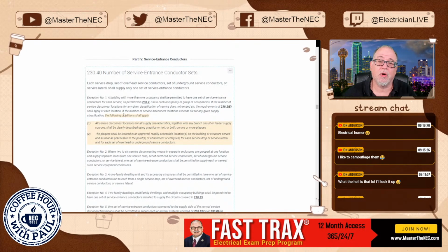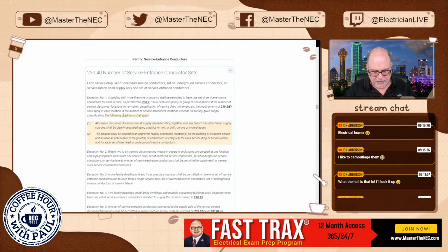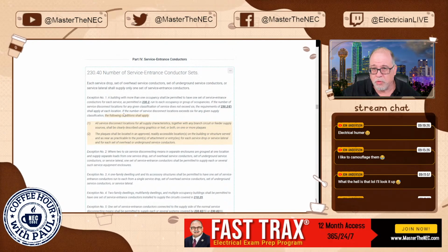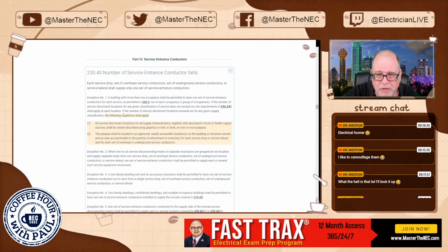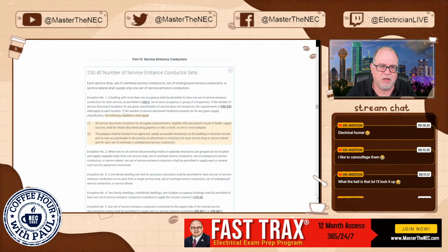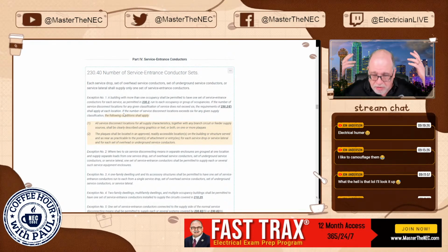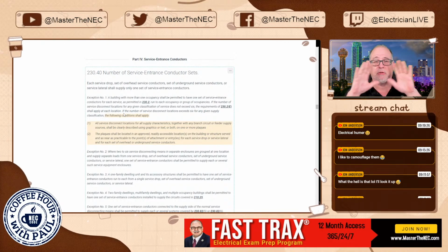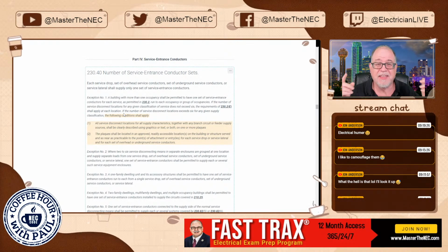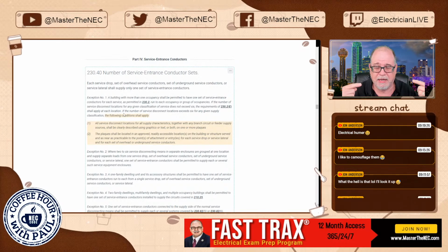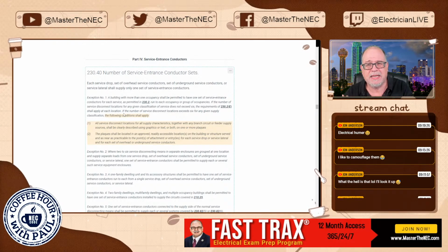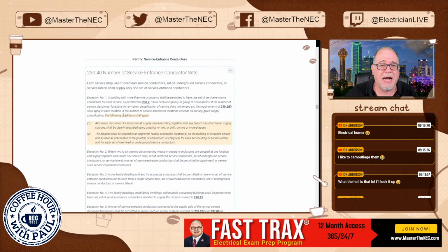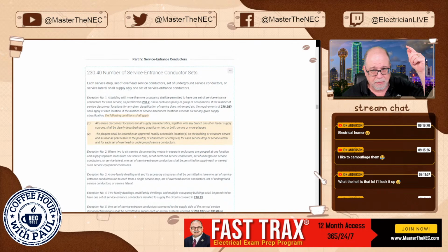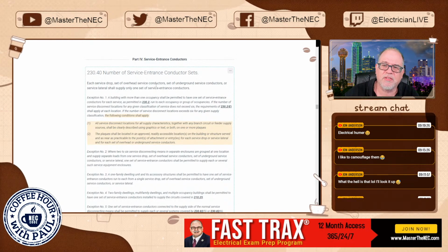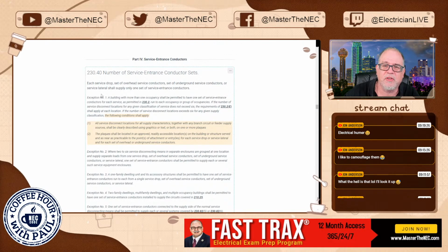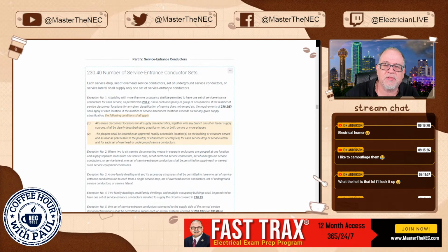So other than that, let's see here. Okay, so are you familiar with the rule where, when you're going to a building, you can't have more than a certain number of services that you can take to a building, right? Well, this has to do with service entrance conductors. Now, let's say I had an apartment complex and I bring a service drop down to it, and my service conductors stay on the outside of the building, and it wraps around the building and then penetrates into individual apartments, let's say, right? So that is permitted under exception number 1. Why? Because the code originally says each service drop, say coming from a pole to the building, set of overhead service conductors or set of underground service conductors shall supply only one set of service entrance conductors.